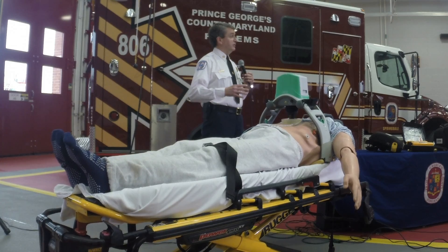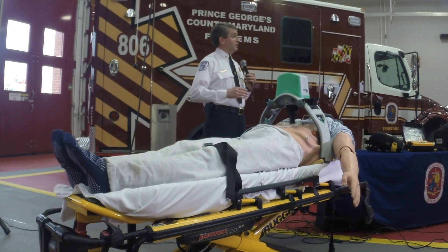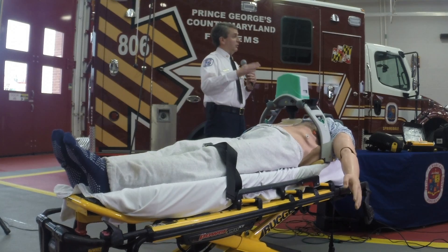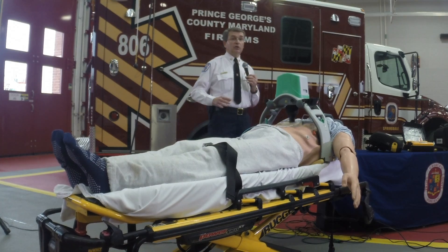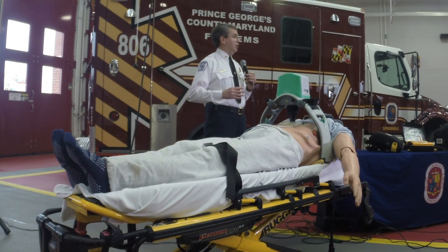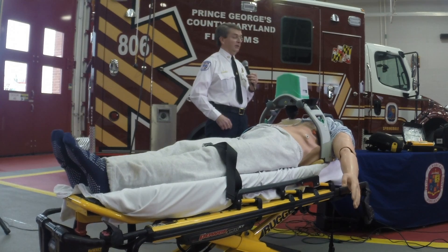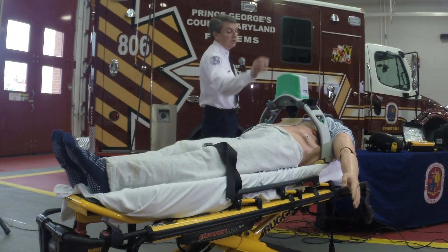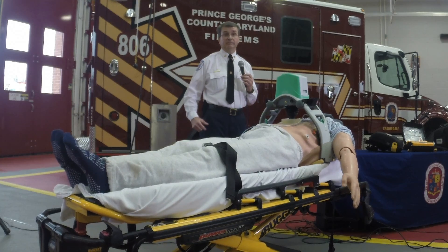It's actually a very safe mode to transport patients. If you have to take somebody down a flight of stairs, in the past it was very difficult to do CPR walking down a flight of stairs — but with this on the patient, CPR can continue. The whole high performance CPR is about doing continuous CPR and limiting the hands-off time for a patient. This will accomplish that. If I need to pause it, I just pause it, check for a pulse, and if there's no pulse, I start it back up again and it takes over.